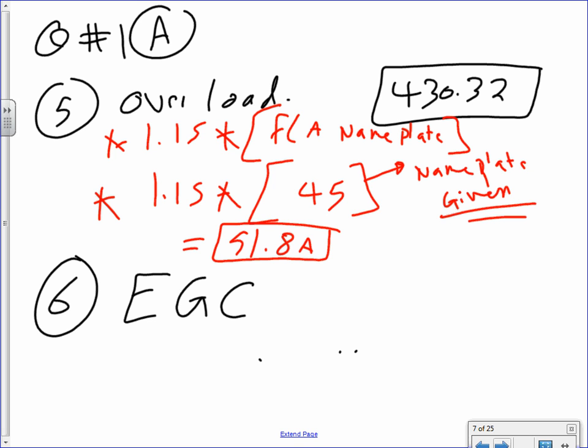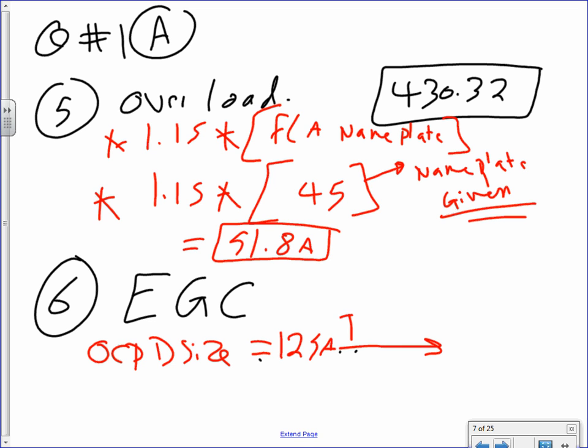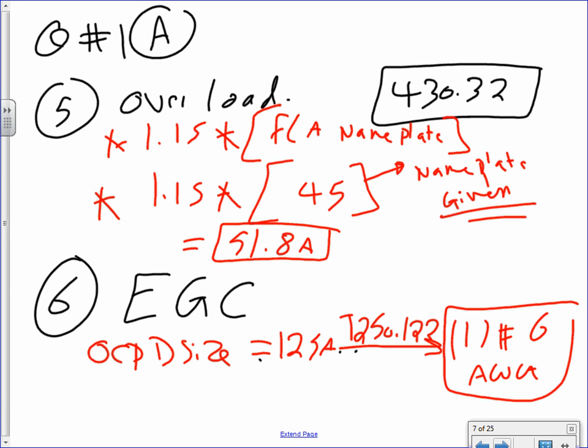The last thing is the equipment ground conductor. You go to the overcurrent protection device size, which was 125 amp. Take this one to Table 250.122. That will get you one conductor, number 6 AWG. Hopefully that conductor will be part of your NM cable. So we're not going to have a separate conductor. Typically it will be part of your NM cable. 250.122, number 6 AWG, part of your NM cable.